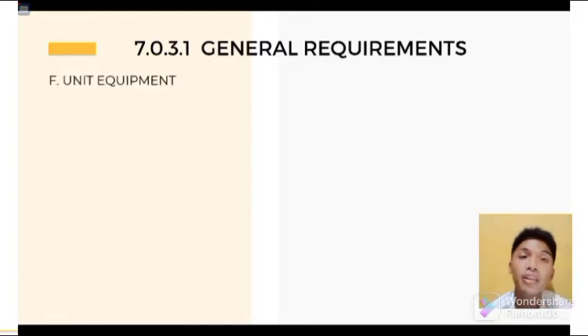Letter F, unit equipment. Individual unit equipment for emergency illumination shall consist of the following. There are 4. First will be a rechargeable battery. Number 2 will be a battery charging means. Number 3 is a provision for one or more lamps mounted on the equipment or shall be permitted to have terminals for remote lamps or both. Number 4 is a relaying device arranged to energize the lamps automatically upon failure of the supply to the unit equipment.